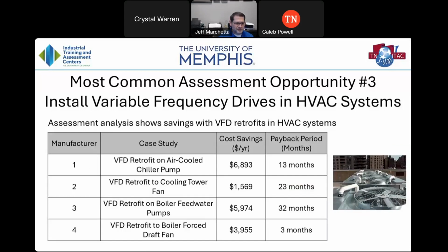Next slide. So here are some things that we've recommended very commonly when we visit plants that involve VFD drives and HVAC systems. We've recommended them for air-cooled chiller pumps, cooling tower fans, and on the heating side, boiler feed water pumps, boiler forced draft fans. You can see the paybacks and cost savings there - everything is less than a 2.5 year payback.